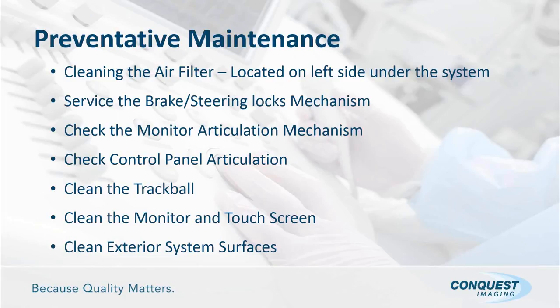So moving further into preventative maintenance, once you actually start the preventative maintenance, you successfully backed up the system. We want to start by cleaning the air filter. The air filter is located on the lower left-hand side of the system, and it just slides out. It's a very easy filter to get to. You need to make sure to service the brakes and steering lock mechanisms. This is a fairly new system. We haven't had a lot of problems with the brake mechanisms or steering mechanism for that matter, but it's important to understand that this is an accreditation requirement. ACR, for example, requires that you check the functionality of brakes and steering.